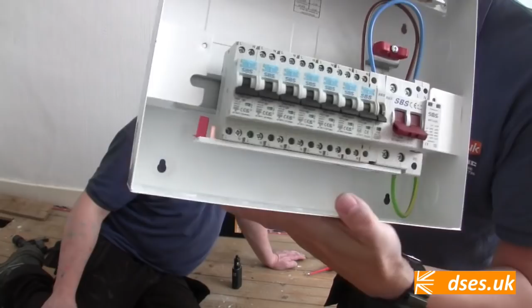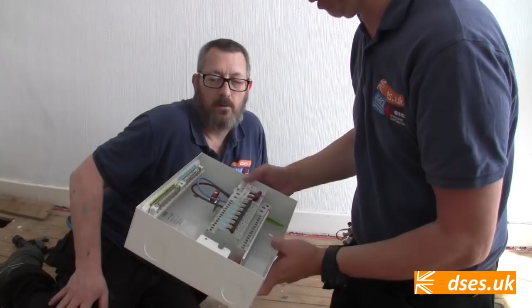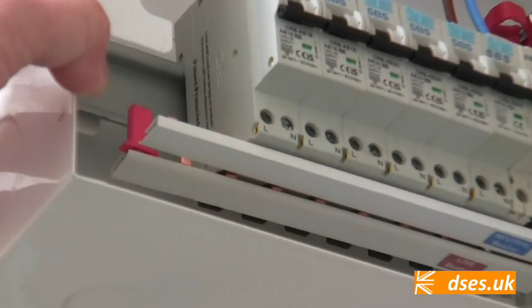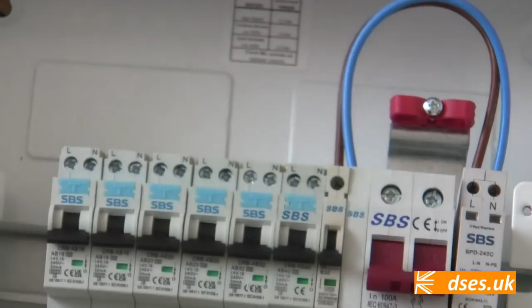You tell them how you want your consumer unit configured, and they configure it. This consumer unit has within it a rather exciting development, in that it's a dual busbar arrangement - you have your line and neutral busbars down the bottom there. So these are all 2-pole devices, directly on the busbar, which, as you can see from the lack of wiring here, means you don't have neutral leads flying off the RCBOs. They put it together for you in the configuration you ask for, and there's less assembly you have to do on site - you know that this is all torqued up. What do you think about that, Nigel? A dual busbar arrangement, hot or not?